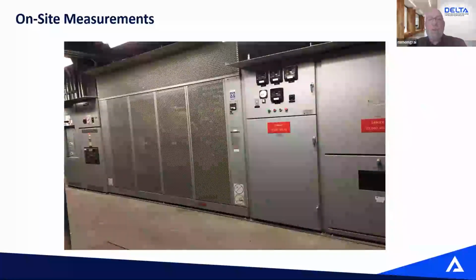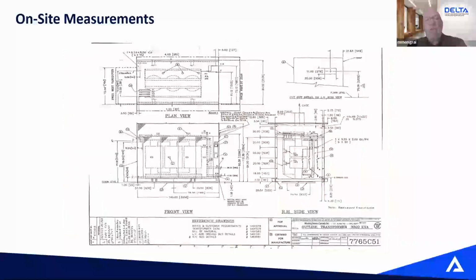That's an example, a project we did a few years ago, an old Westinghouse transformer sitting between a medium voltage and a low voltage gear. So that needs to be entirely replaced. Fortunately for that project, we were able to grab from the building owner a set of the drawings of the existing transformer. Usually, we don't only rely on the drawing because over the years there might have been modifications or changes to the equipment.